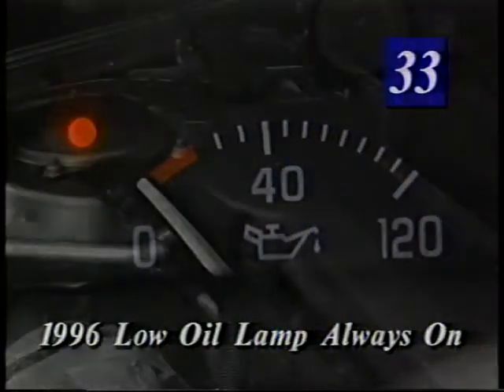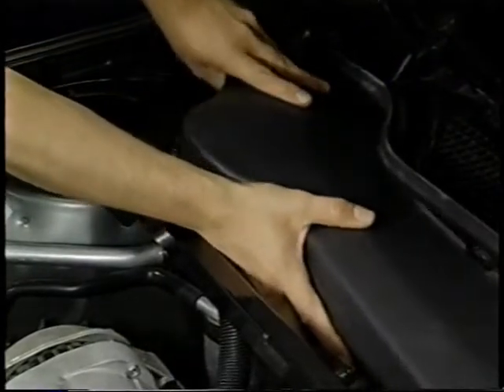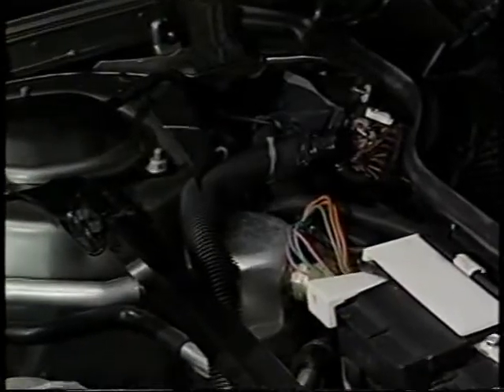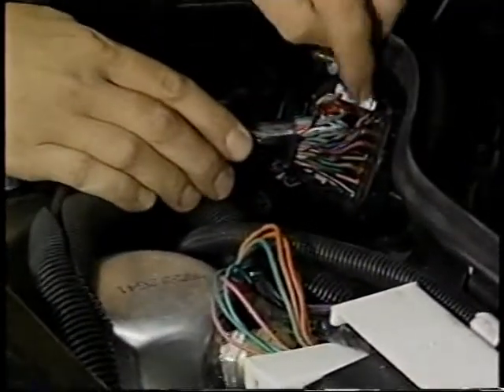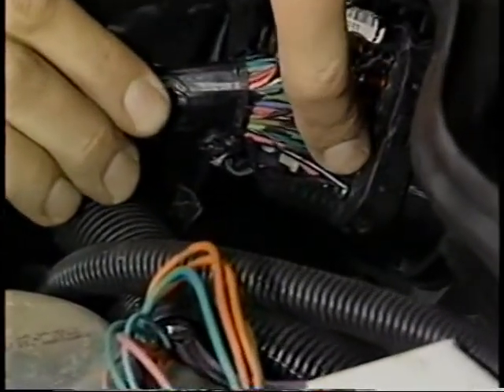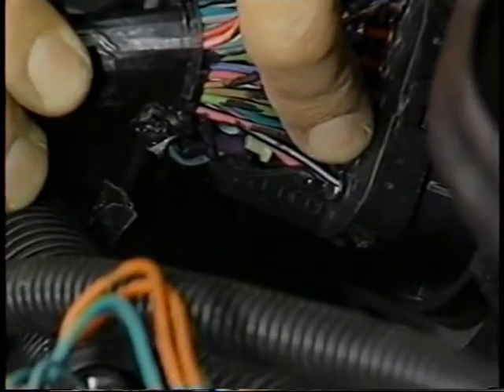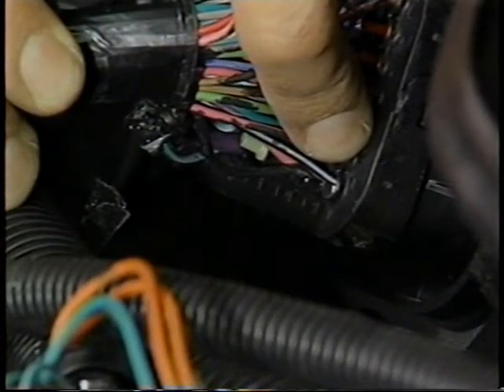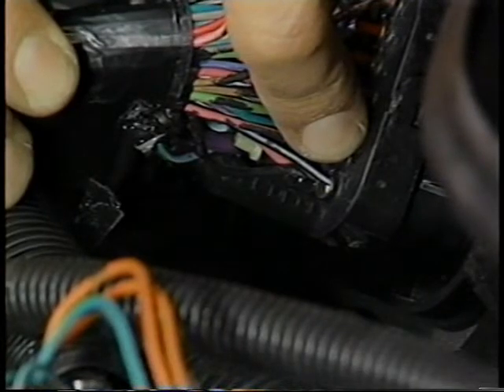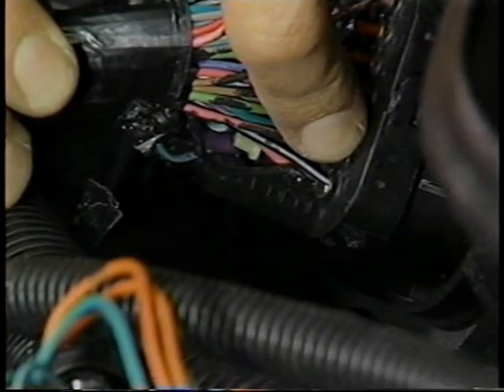Conditions where the low oil pressure lamp is always on can be caused by a broken wire going to the 66-way connector. Plant technicians have reported instances where the black and white ground wire is broken. Oftentimes, the insulator is only stretched while the wire is broken. This can make diagnosing these conditions difficult.